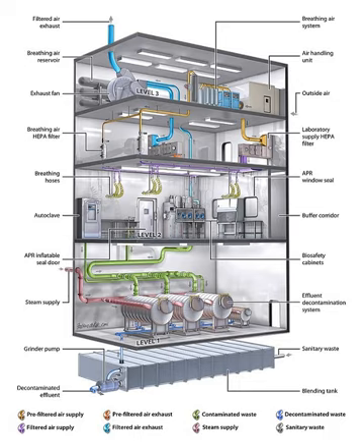The cabinets themselves are required to have seamless edges to allow for easy cleaning. Additionally the cabinet and all materials within must be free of sharp edges in order to reduce the risk of damage to the gloves. In a protective suit laboratory, all work must be done in a class 2 biosafety cabinet by personnel wearing a positive pressure suit. In order to exit the BSL-4 laboratory, personnel must pass through a chemical shower for decontamination, then a room for removing the positive pressure suit, followed by a personal shower.